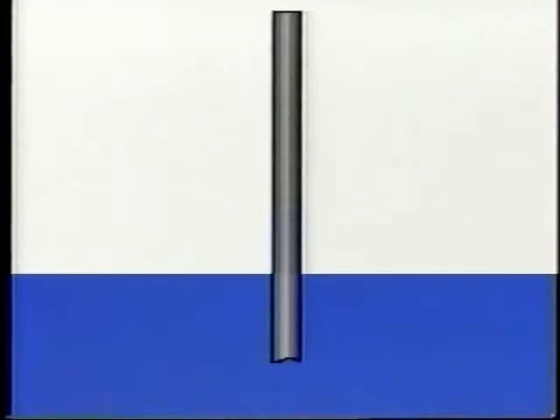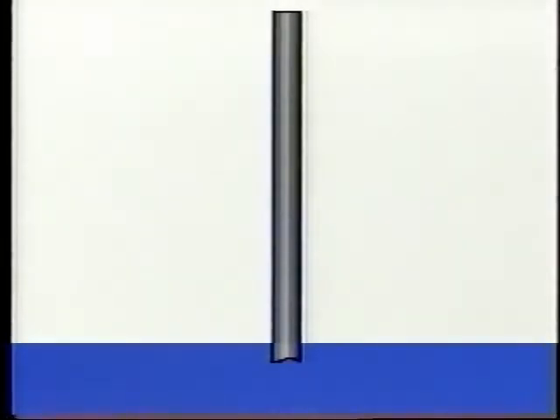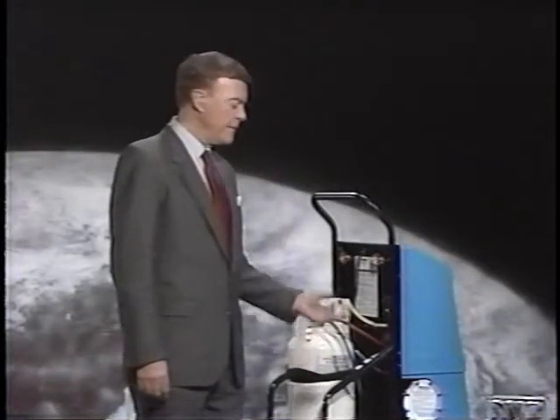Charging is the same, with one exception. Inside the tank, the tube extends to within an inch of the bottom of the tank. This design allows liquid R12 to be drawn from the bottom of the tank without turning it over.